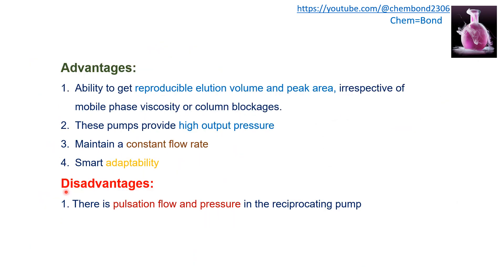Advantages and disadvantages of the reciprocating pump: similar to the syringe type pump, it produces reproducible elution volume and peak area irrespective of mobile phase viscosity and column blockages. It offers high output pressure, constant flow rate, and smart adaptability. The disadvantage is pulsating flow and pressure, but this can be avoided using a pulse damper.